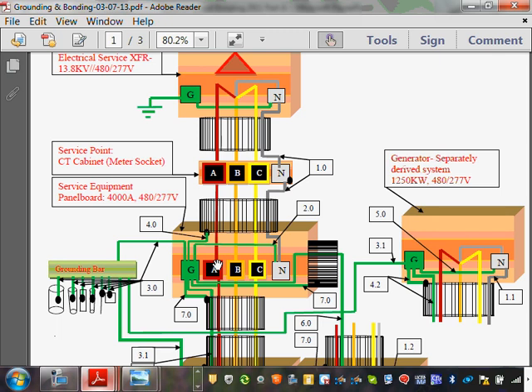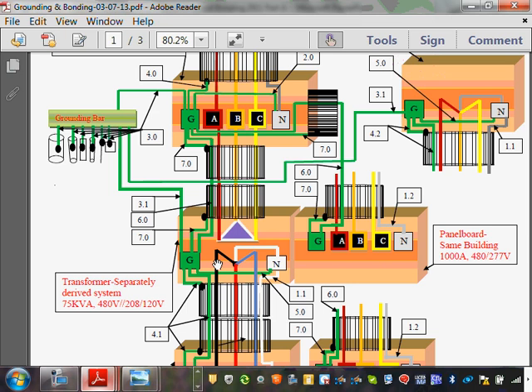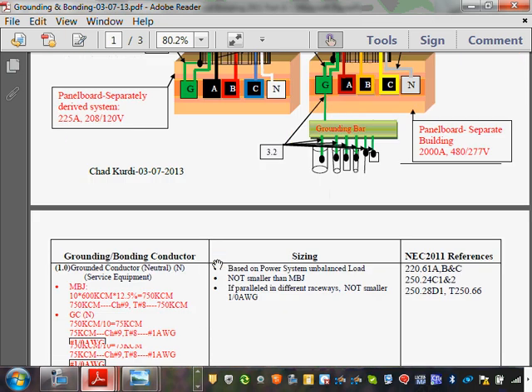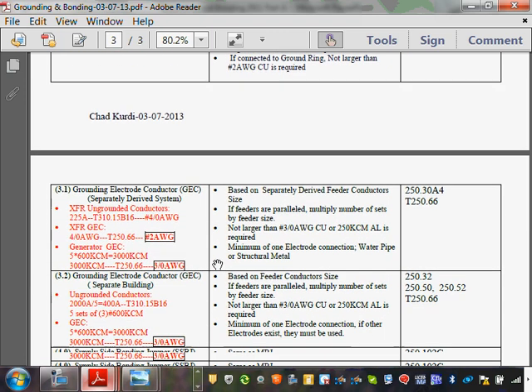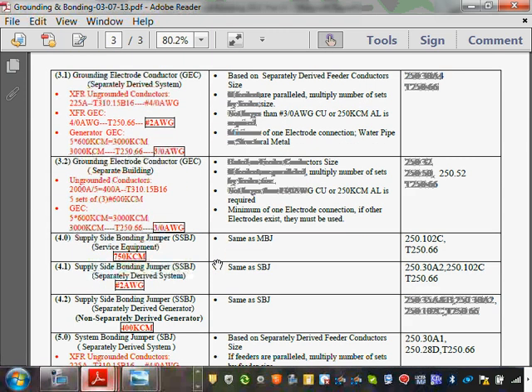Okay, so let's size the 4.0, bonding the conduits at the service. I want to remind you that it could also be a wedge. It doesn't have to be a wire. You'll see later on. So if you go to 4, here's my 4. Look what it says: supply side bonding jumper. It's called SSBJ. In NFPA NEC 2011, and even before, actually 2008, they started calling it supply side bonding jumper. That's the technical name for it.